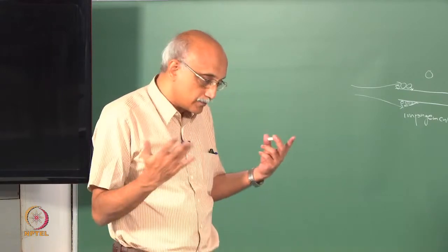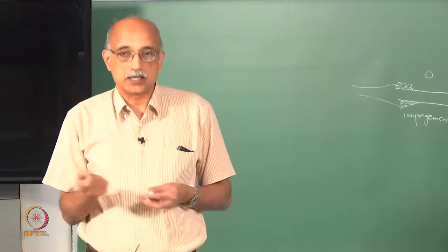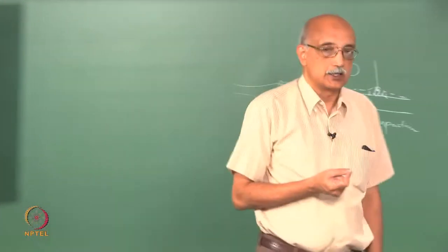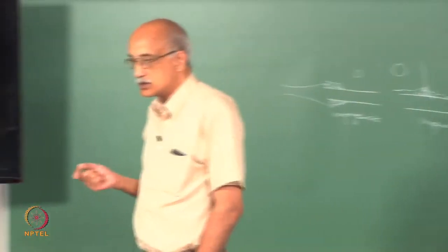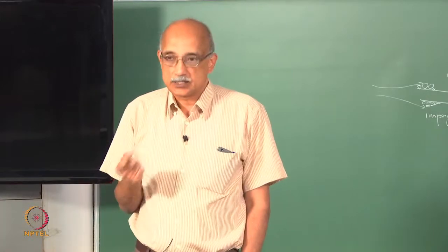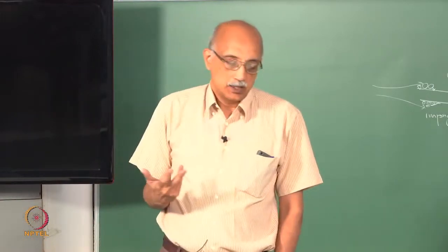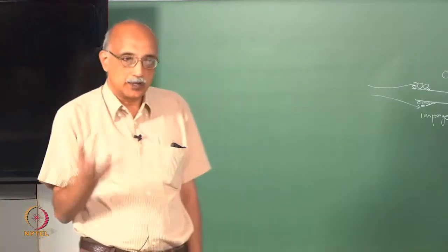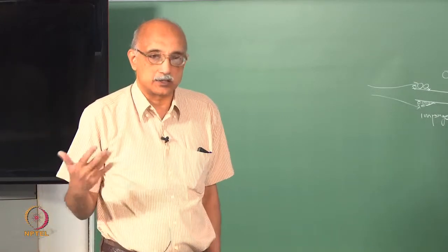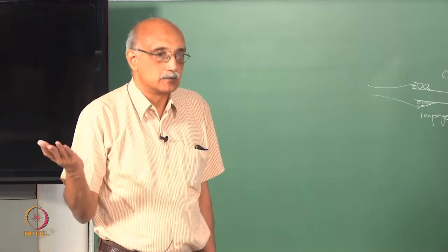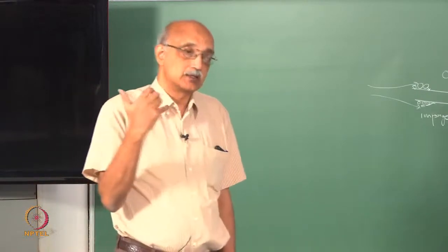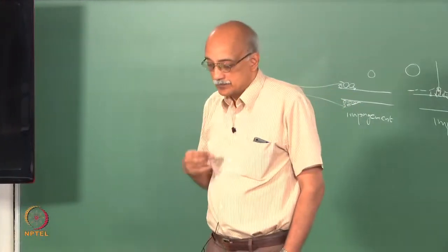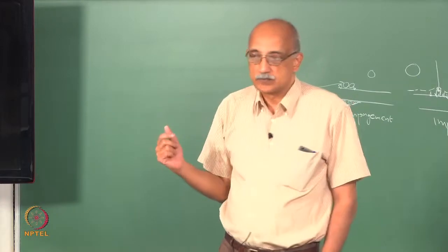So, people thought about it and they came up with techniques that are based on light scattering. Light scattering is now the most commonly used method for characterizing the sizes of individual particles as well as population of particles. And the reason for that is it is a simple technique. It is a push button technique. The operator does not need to know a lot of science or technology to be able to use it. Anybody can use the instrument. Of course, the design of the instrument, the calibration, all of that has to be done by specialists, but once the equipment is provided to a lab, it can be used very simply.